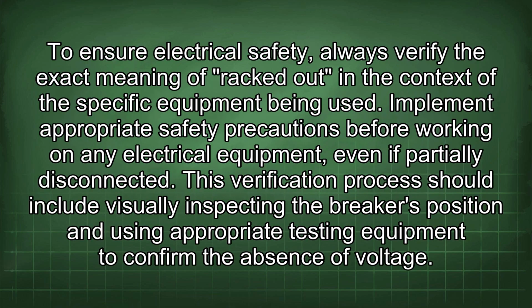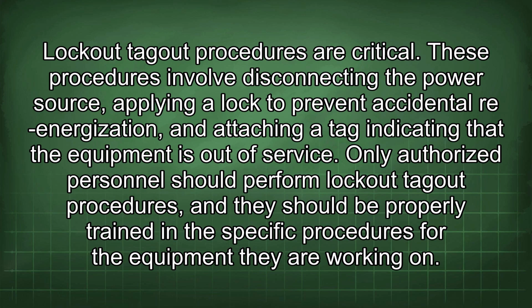To ensure electrical safety, always verify the exact meaning of racked out in the context of the specific equipment being used. Implement appropriate safety precautions before working on any electrical equipment, even if partially disconnected. This verification process should include visually inspecting the breaker's position and using appropriate testing equipment to confirm the absence of voltage. Lockout-tagout procedures are critical. These procedures involve disconnecting the power source, applying a lock to prevent accidental re-energization, and attaching a tag indicating that the equipment is out of service.